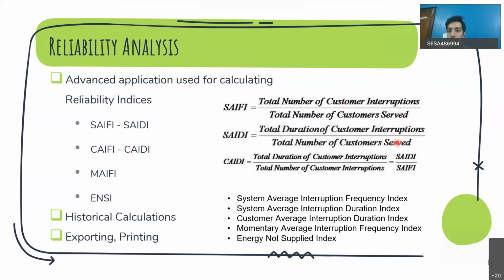Similarly, SAIDI is the duration - if you cancel out the total number of customers, what's left is duration. So the SAIDI value on a particular network for a particular time period will be the duration of outage. For example, if SAIFI is 5 and SAIDI is 5 for a particular network in a particular month, that means for that feeder there were 5 outages, denoted by SAIFI, and a total duration of 5 hours of outage, denoted by SAIDI - probably each outage lasting 1 hour, 5 times, totaling 5 hours. This is how the performance of a distribution utility is measured by these indices.